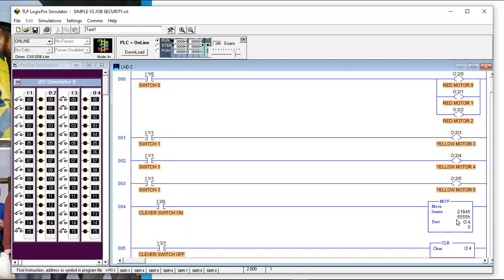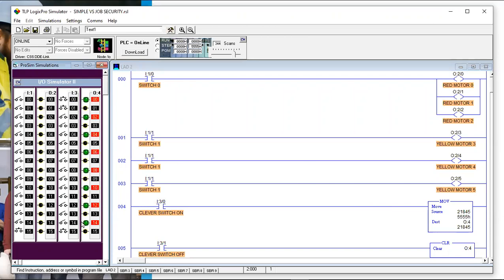Instead of individual inputs and outputs, what we've done here is move an integer — 21,845 — to a destination file of output four. Let's see if it works: one push of the button, and yes, all those outputs came on. It's pretty slick. But if you had to troubleshoot this and somebody says output four-four isn't coming on, there's no reference to that anywhere in the program.